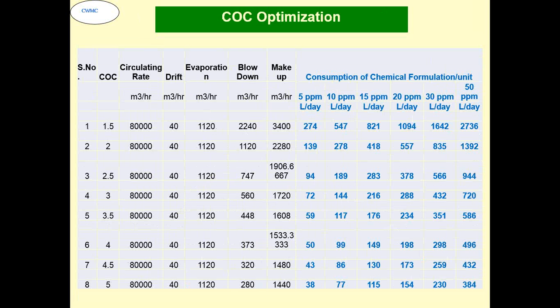This is what you can see, typically a cooling tower with say 80,000 meter cube circulation rate, and the blowdown and makeup rate that you can see, and you can see at different COC your total chemical consumption goes down. So even though probably you might be doing a higher dosage of chemical, that is an economical method of treating at that level. So you need to optimize your treatment program based on your site conditions and the COC that can be achieved properly.